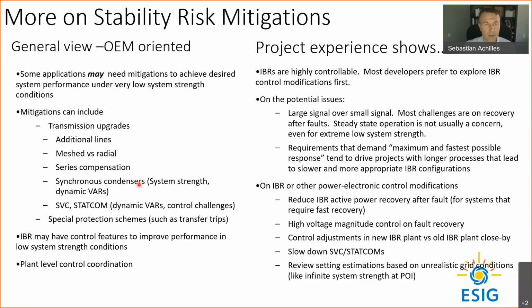Synchronous condensers can improve the system strength. SVC and STATCOMs are a dynamic source of VARs, so they could help. They have control challenges, as we saw before. There could be some interactions, but as long as you take care of the interactions, this could be a mitigation. And then in some cases, you could have special protection schemes where you reduce the amount of power injected into the system in extreme conditions to avoid unintended trips. And the other option, of course, as I mentioned before, is to modify controls or tuning in the inverter-based resources, and in some cases in the plant level controls.